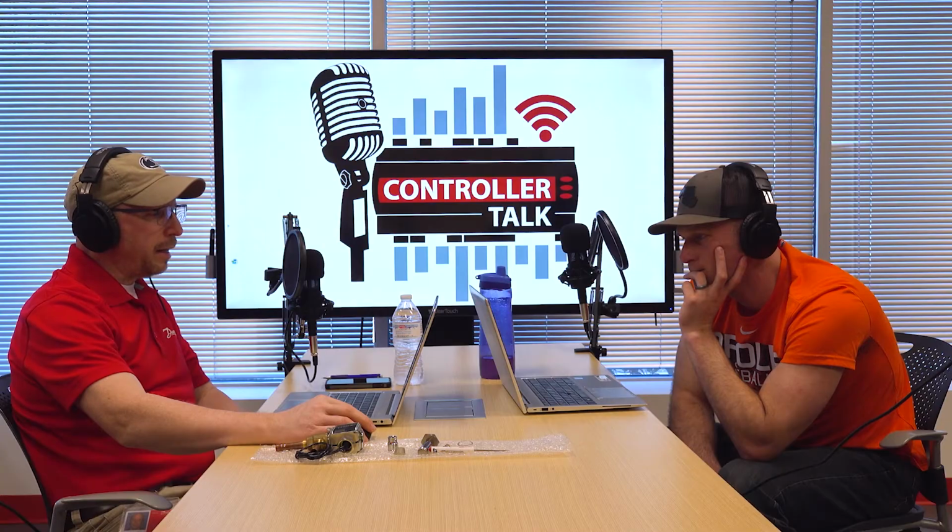Yep. So, Chris, we get this occasional call about distributors that have an orifice inside, and there's a pressure drop through that orifice in the distributor. Yep. And from our standpoint, we wouldn't normally think that you even need one in there. Yep. But a lot of times there is one in there. And you can get icing on the distributor, you can get flashing, and what are people supposed to do about that?